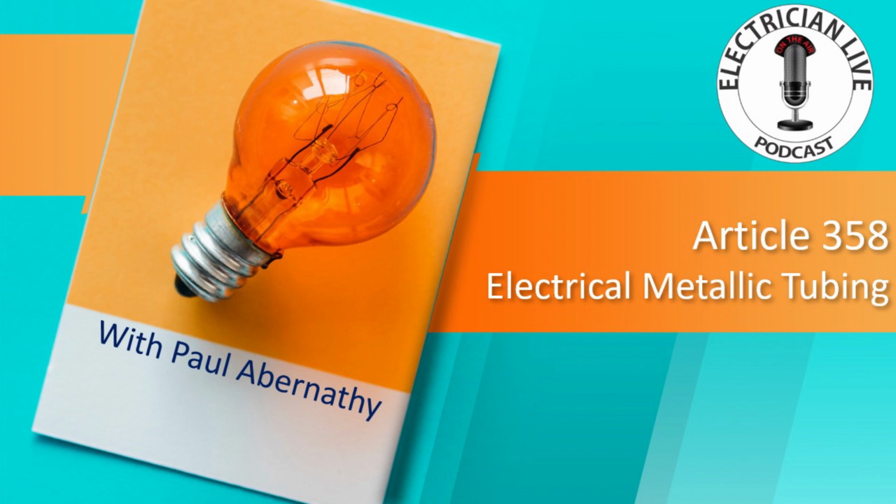So what is the definition of EMT? It is an unthreaded, thin wall raceway of circular cross-sectional design for the physical protection and routing of conductors and cables, and for use as an equipment grounding conductor when installed utilizing appropriate fittings.